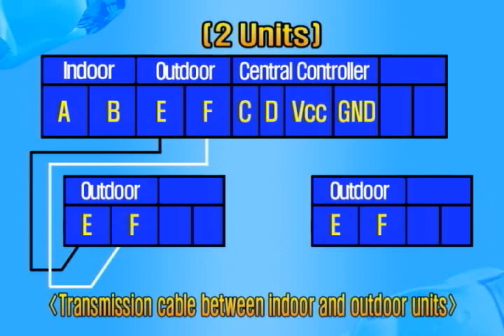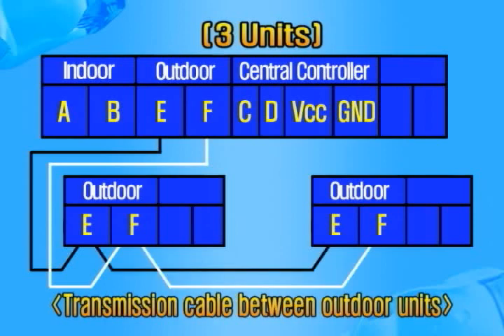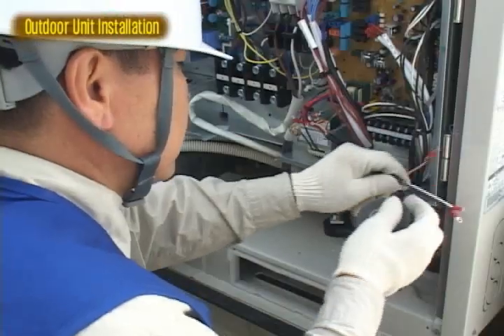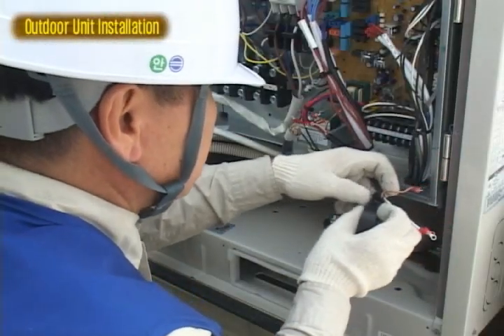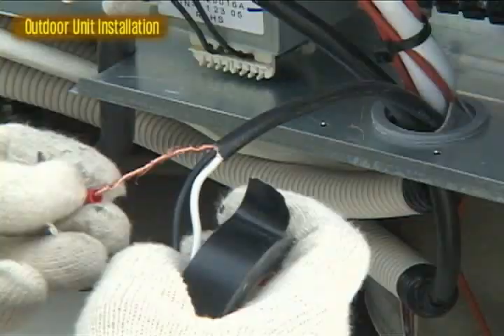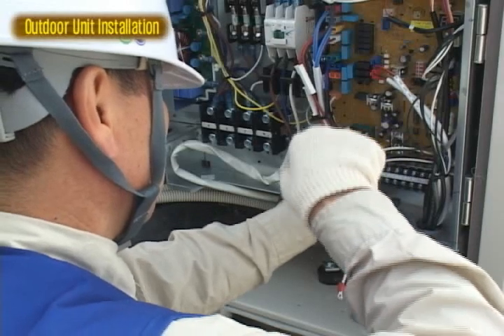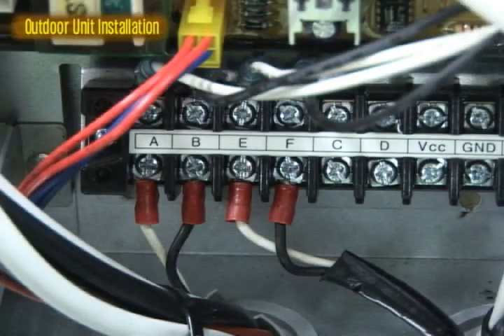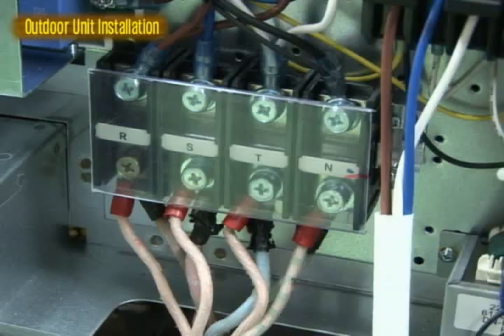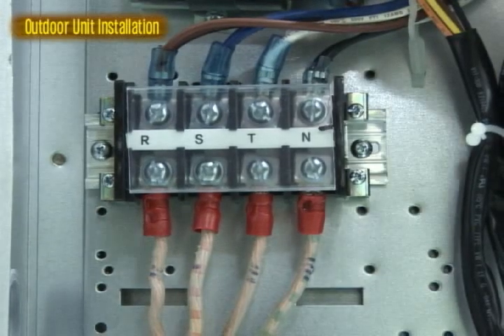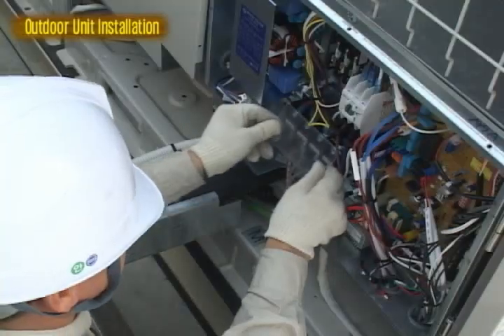The connection of transmission line with more than 2 outdoor units is like the following. For grounding the transmission cables from each indoor unit, peel out cables, combine them, and connect to the earthing terminal. And also, when installing more than 2 units, you must connect the main power supply to the main outdoor unit and sub-outdoor unit. Finally, check all the wiring status and fix the cord clamp.